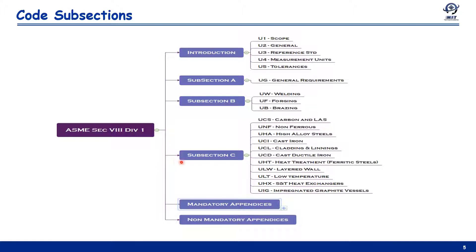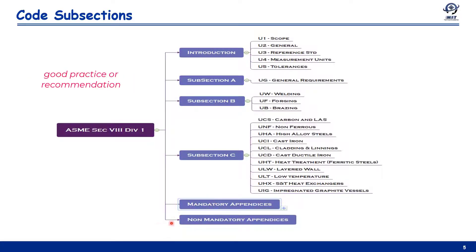Subsection C contains requirements related to specific materials: UCS for carbon and low-alloy steels, UNF for non-ferrous, UHA for high-alloy steels such as stainless steel, UCI for cast iron, UCL for cladding and linings, UCD for cast ductile iron, and other sections. Mandatory appendices cover subjects not addressed elsewhere in the code and are mandatory when applicable. Non-mandatory appendices provide information and suggested good practices that are not mandatory.